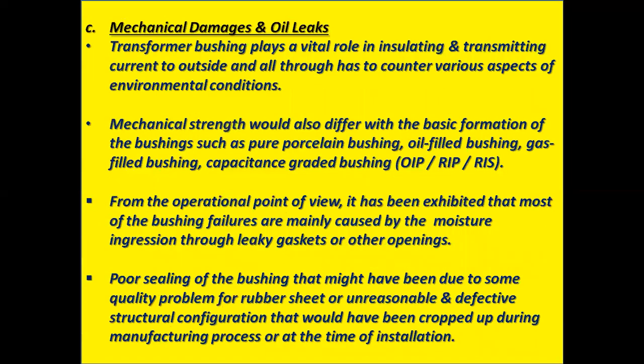Mechanical damages and oil leaks. The transformer bushing plays a vital role in insulating and transmitting current to the outside, and all through has to counter various aspects of environmental conditions. Mechanical strength would also differ with the basic formation of the bushing, such as pure porcelain bushings, oil-filled bushings, gas-filled bushings, and capacitance graded bushings, that is OIP, RIP, RIS, RIF.